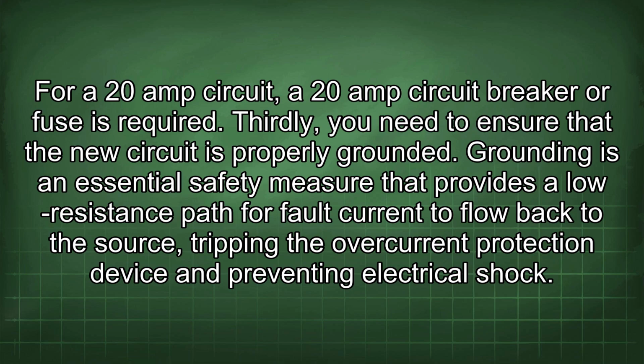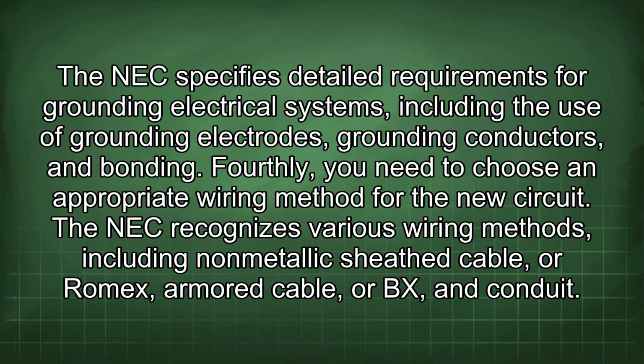Thirdly, you need to ensure that the new circuit is properly grounded. Grounding is an essential safety measure that provides a low resistance path for fault current to flow back to the source, tripping the overcurrent protection device and preventing electrical shock. The NEC specifies detailed requirements for grounding electrical systems, including the use of grounding electrodes, grounding conductors, and bonding.